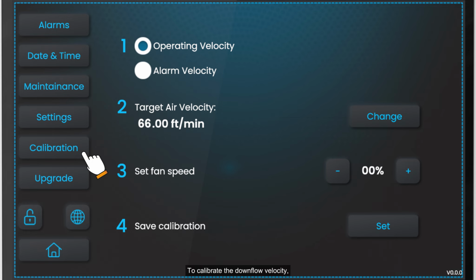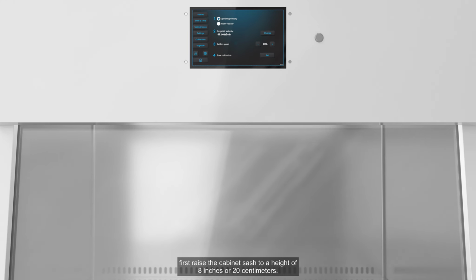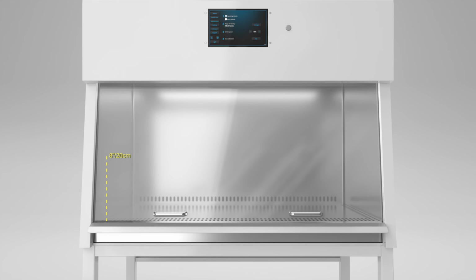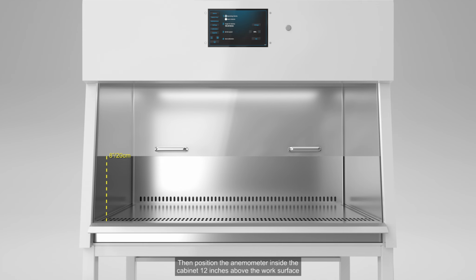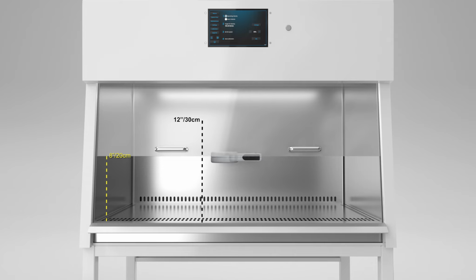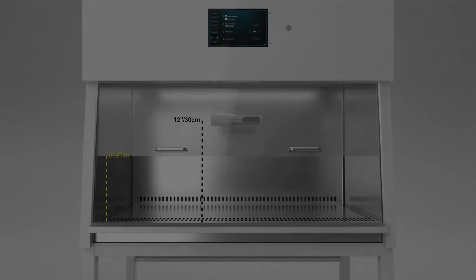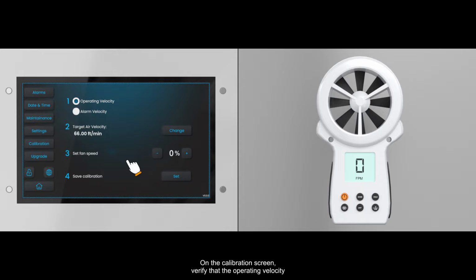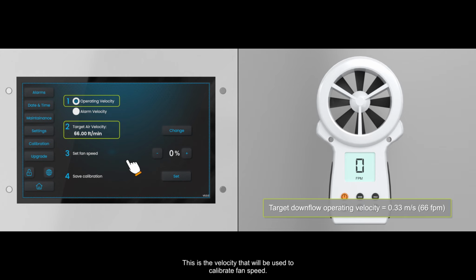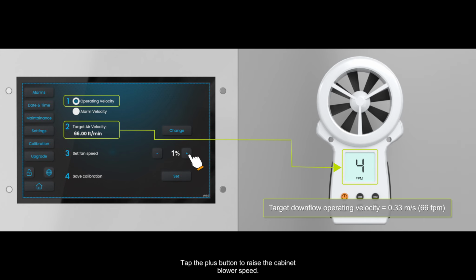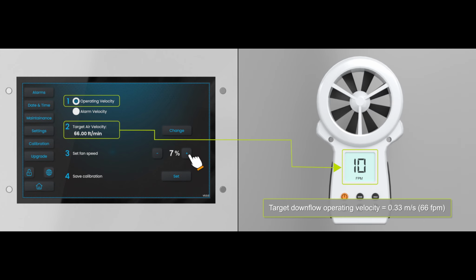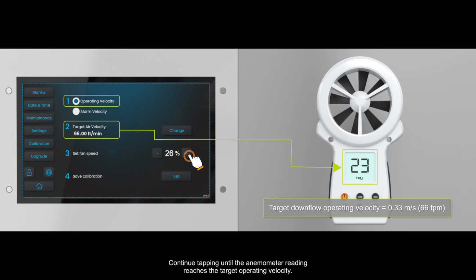To calibrate the downflow velocity, first raise the cabinet sash to a height of 8 inches or 20 centimeters. Then position the anemometer inside the cabinet 12 inches above the work surface and turn it horizontally. On the calibration screen, verify that the operating velocity option is selected and note the target air velocity set point. This is the velocity that will be used to calibrate fan speed. Tap the plus button to raise the cabinet blower speed. Continue tapping until the anemometer reading reaches the target operating velocity.